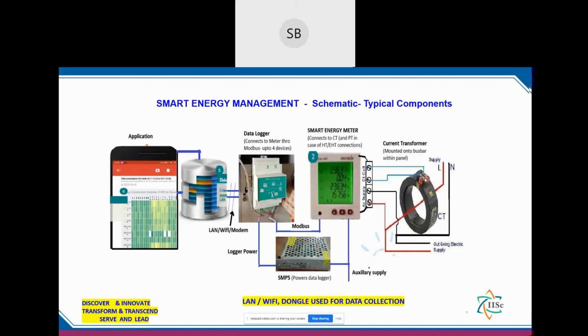You have a CT, the current transformer, used for measurements. From the current transformer, two terminals go to the smart energy meter. Normally, we connect the smart meter to the CTs of all departments. In case of an EHT, extra high tension or high tension connection, we use the PT terminals instead. That is the only difference; apart from that, everything remains the same.